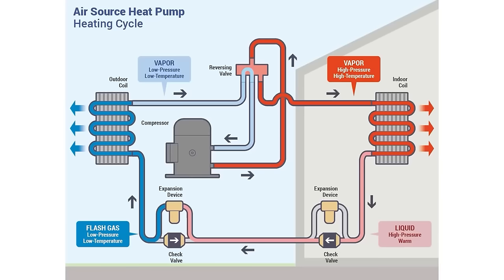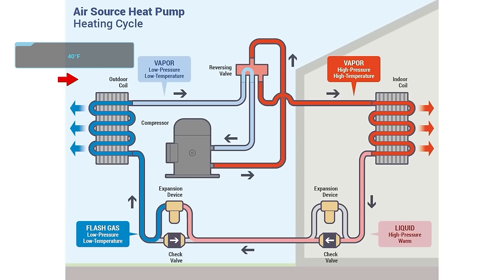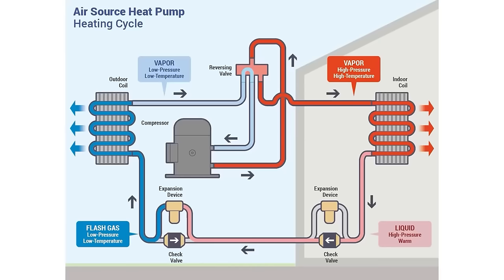In heat pump heat mode, your evaporator coil is outside and your condenser is inside. When it's 40 degrees outside, suction pressure is going to be much lower than in cooling mode — operating closer to how a refrigeration cooler works. That's going to increase compression ratio significantly. The colder it gets outside, the higher the compression ratios go because the lower the suction pressure goes, making the system less efficient and producing less capacity.